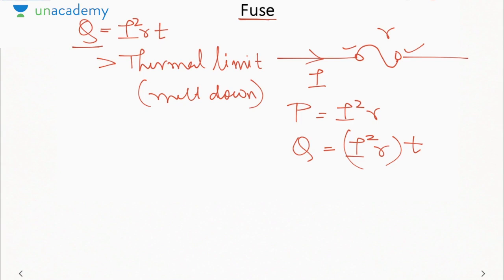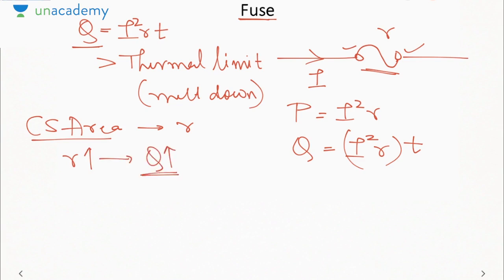Okay. Now there are two things: how to design the cross sectional area and the length of fuse. Okay. Now cross sectional area, it is designed on the basis of resistance, because if you increase resistance, Q increases, so it will exceed the thermal limit easily. But if you decrease the resistance, then Q decreases, and hence it will take more time to exceed the thermal limit, because the threshold condition is that Q is equal to thermal limit.